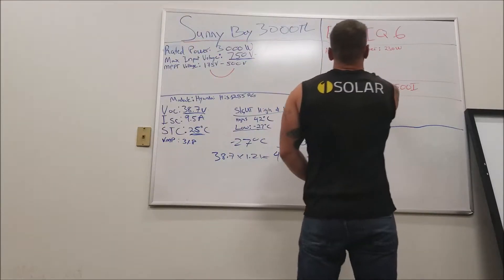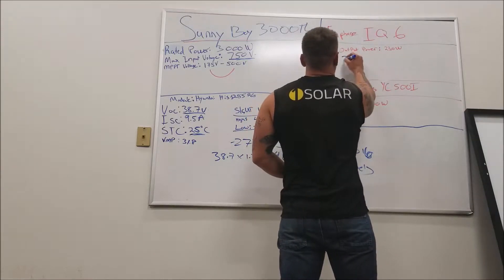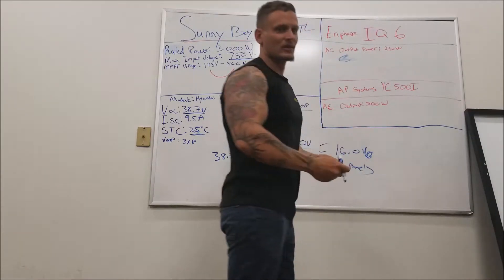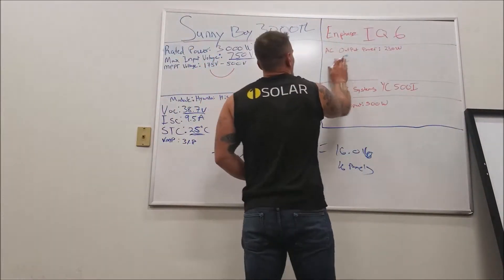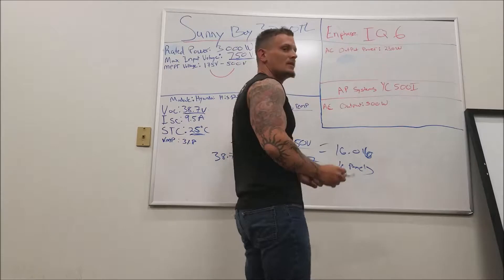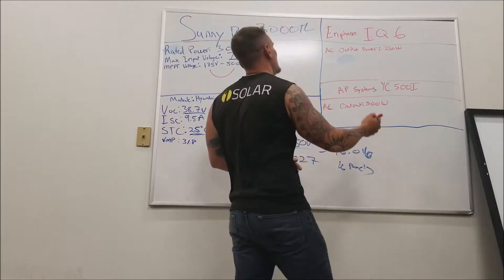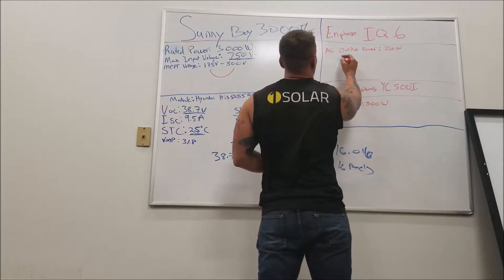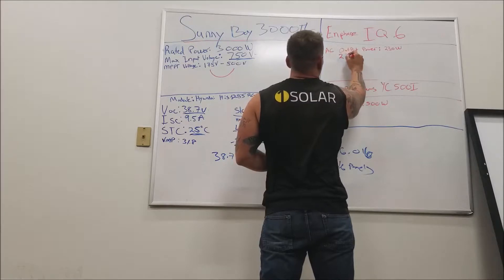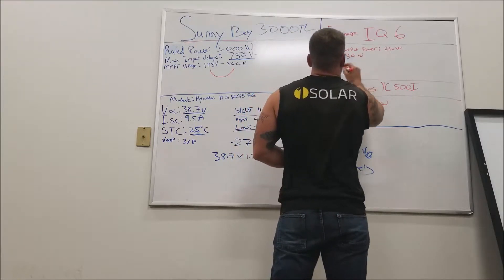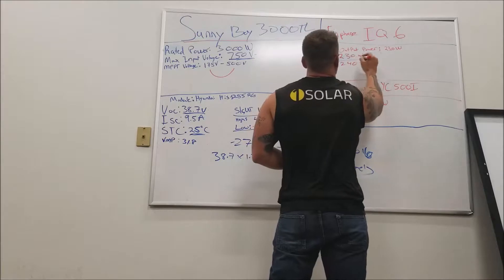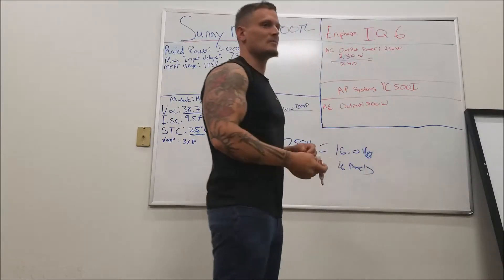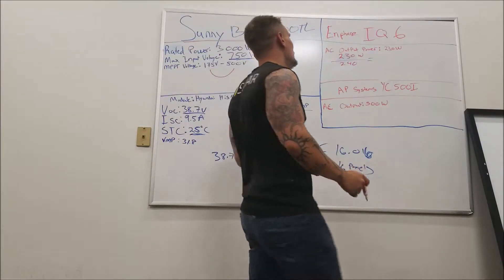Now for branch circuits — 230 watts. This is a single-family dwelling, so we're at 240 volts residential in the United States. So 230 divided by 240 gives us 0.958 amps, because watts divided by volts gives us amps.